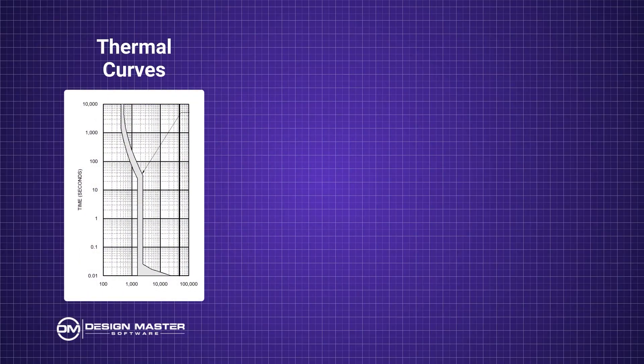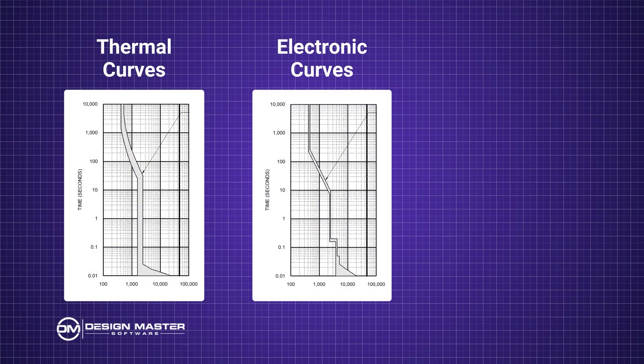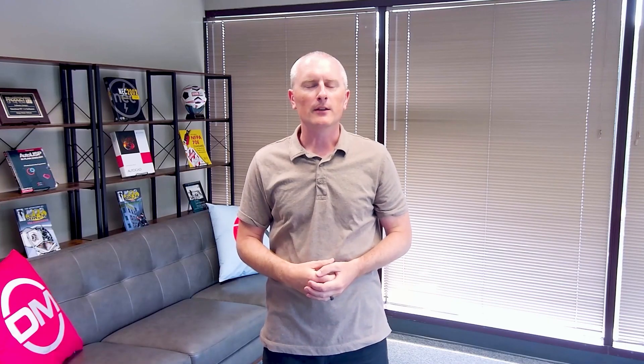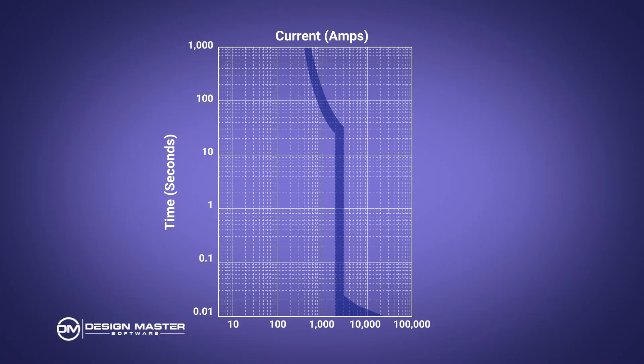There are three basic shapes of curves we'll talk about: thermal curves, electronic curves, and fuses. The thermal curves are for thermal magnetic breakers and they have three parts. On the left-hand side you have the rating of the breaker itself, and you don't want it to trip immediately when the current hits that rating, so that's usually a fairly long trip time.